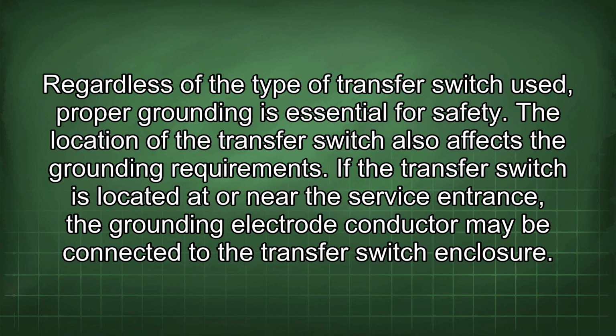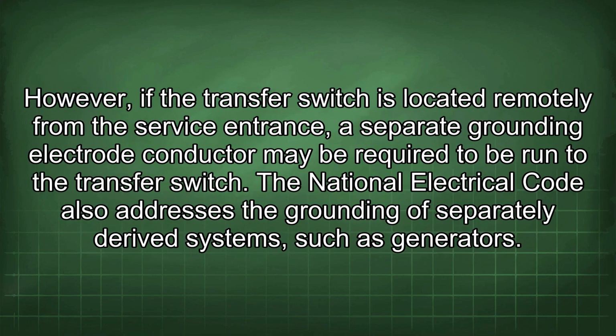If the transfer switch is located at or near the service entrance, the grounding electrode conductor may be connected to the transfer switch enclosure. However, if the transfer switch is located remotely from the service entrance, a separate grounding electrode conductor may be required to be run to the transfer switch.